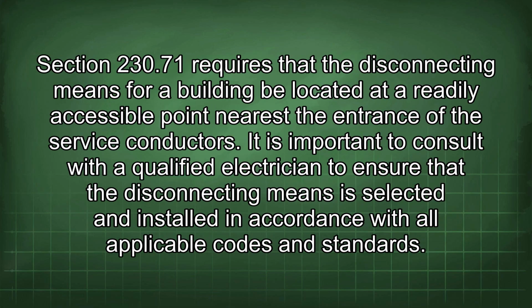Section 230.71 requires that the disconnecting means for a building be located at a readily accessible point nearest the entrance of the service conductors. It is important to consult with a qualified electrician to ensure that the disconnecting means is selected and installed in accordance with all applicable codes and standards.